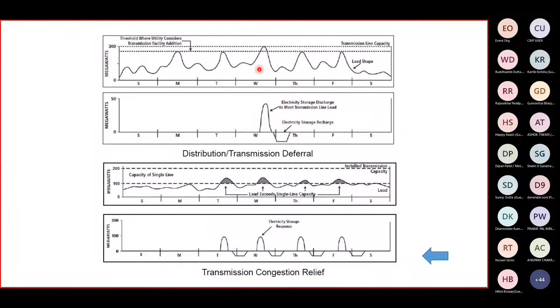Then comes transmission and distribution upgrade deferral. The dotted line shown here is the threshold, and you can see this threshold is crossed only for a few minutes or a few days. This threshold can be met by discharging the batteries, limiting the capacity to the threshold level, and we can avoid or defer the upgrade of a certain line or asset. We can also deploy similar storage at the downstream network to relieve the upstream network. That comes under distribution or transmission deferral.